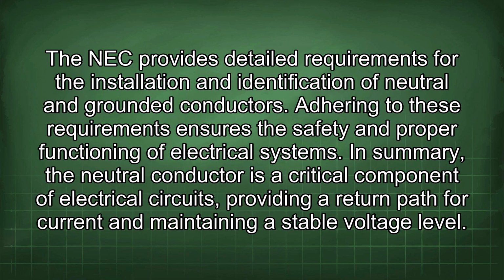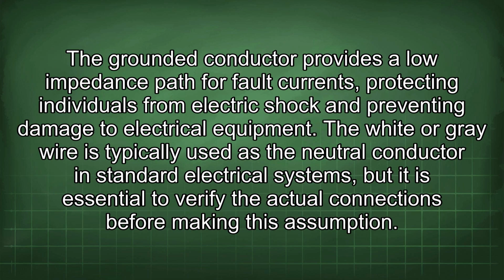The NEC provides detailed requirements for the installation and identification of neutral and grounded conductors. Adhering to these requirements ensures the safety and proper functioning of electrical systems. In summary, the neutral conductor is a critical component of electrical circuits, providing a return path for current and maintaining a stable voltage level. The grounded conductor provides a low impedance path for fault currents, protecting individuals from electric shock and preventing damage to electrical equipment.